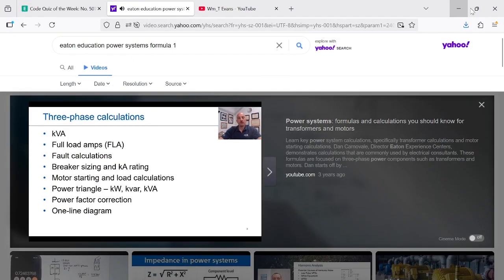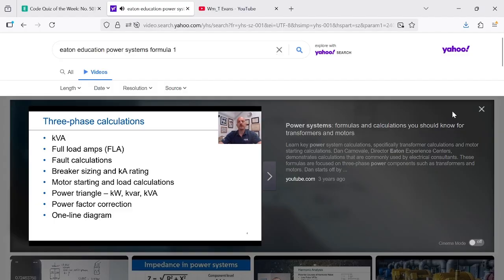In this session, we'll talk about three-phase calculations. So we're going to simplify it to those calculations that are appropriate for three-phase. There will be one or two that are single-phase, but we'll talk about those when they come along. The one thing that's important is really kVA. That's the main equation that we're going to use from the simple calculations of kVA, including voltage and current, and the square root of 3 where appropriate.